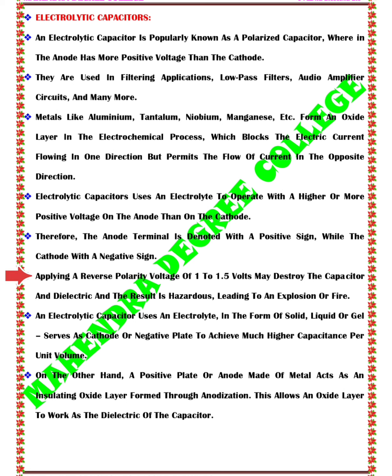Applying a reverse polarity voltage of 1 to 1.5 volts may destroy the capacitor and dielectric, and the result is hazardous, leading to an explosion or fire. For this reason, the polarity is marked on the device housing. Applying a reverse polarity voltage or a voltage exceeding the maximum rated working voltage by as little as 1 or 1.5 volts can damage the dielectric, causing catastrophic failure of the capacitor itself.